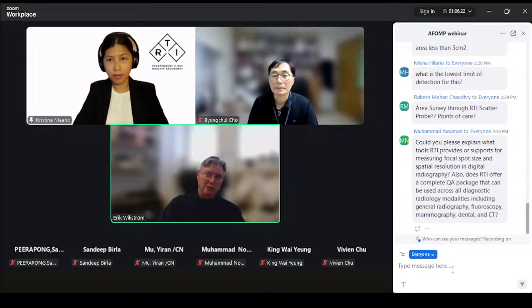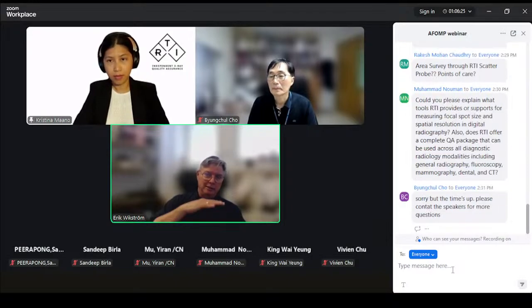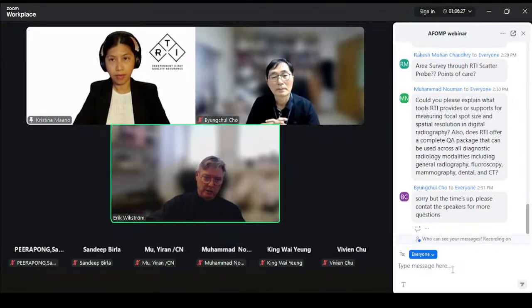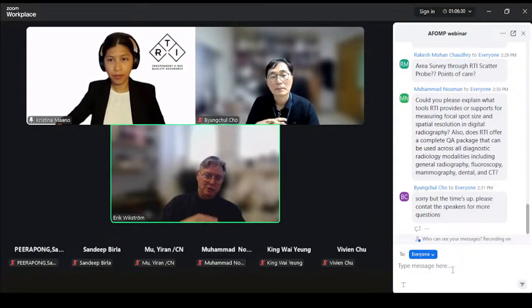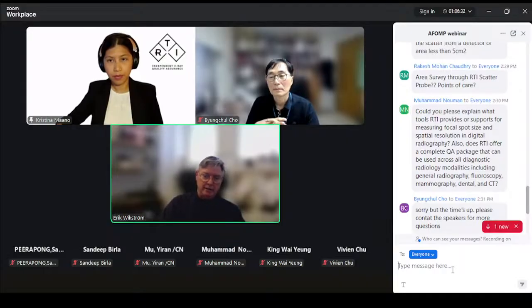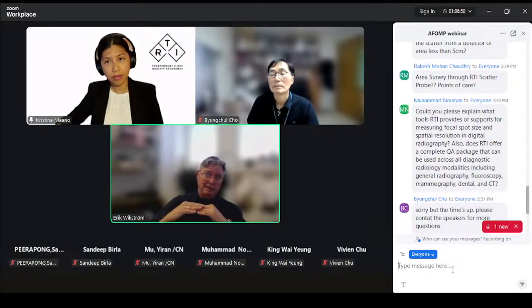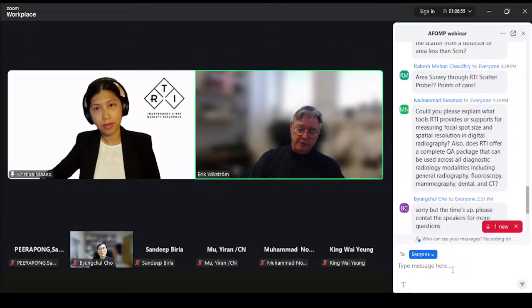Sometimes, after a long period of time, it may even show a negative value if the background radiation drops a little bit. That is the level of sensitivity that we have in the scatter probe. But that doesn't occur very often. So I hope that is a response. It resets to the background radiation and looks at the radiation that is added due to man-made radiation like X-rays.